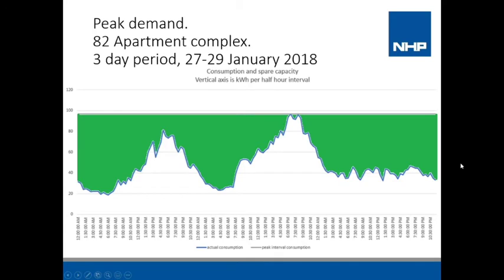I'm going to talk a little bit now about load management. Not going to dive right into the weeds on this, but to address it as a challenge that's going to come up as EVs scale. This chart here is a load profile from an apartment complex in Melbourne. 82 apartments on a series of 3 really hot days. The middle day here was 40 degrees during the day and only dropped to 30 overnight. On this particular day, the grid had real trouble in Melbourne.